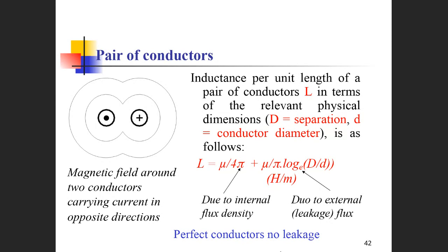Similarly, we can find the inductance for 2-core cables, for 3-core wires, for single-core wires, which results in the inductance, therefore the impedance, therefore the voltage drops in the AC circuit, not DC. In the DC, inductance does not function. In the AC, inductance causes induced voltage drops.